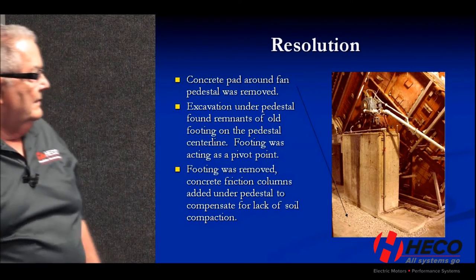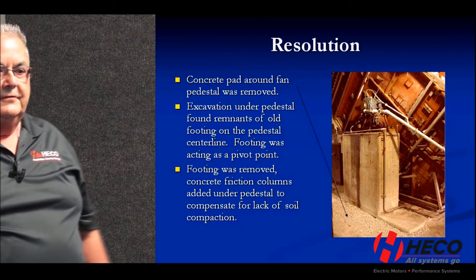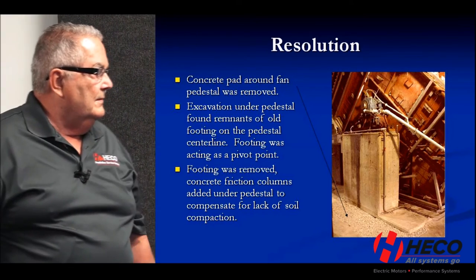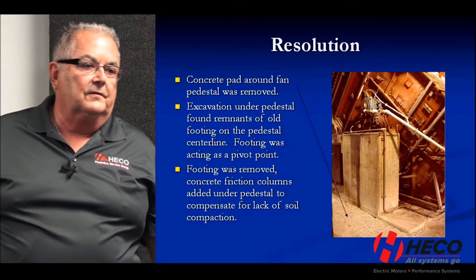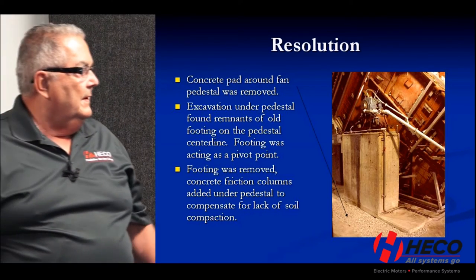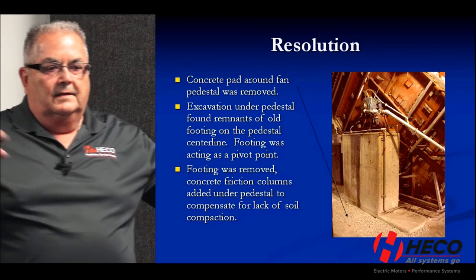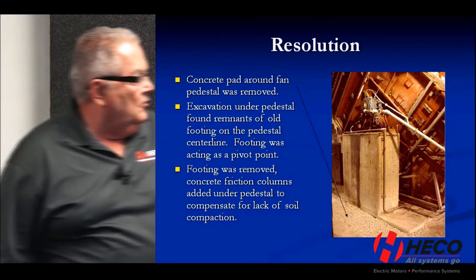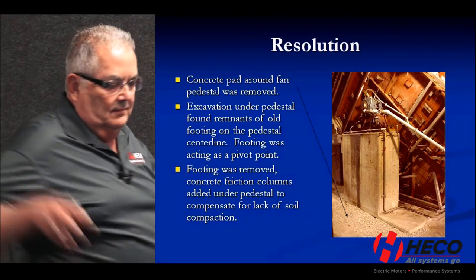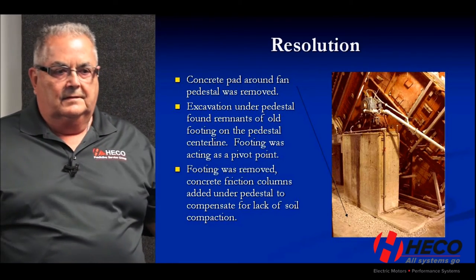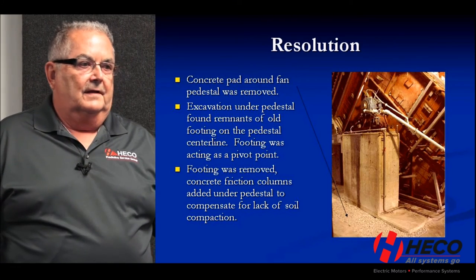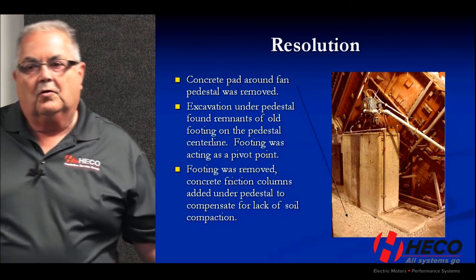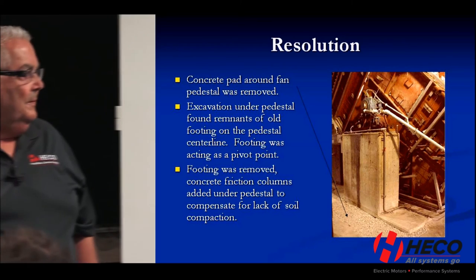We suspected that the footing hadn't been removed and that we now had a fan teetering on top of that wall. So we broke out the concrete and dug underneath — and sure enough, that wall had not been knocked down. Now we needed a fix. They excavated and poured concrete form tubes — column piers — at each corner of the pedestal going down seven to eight feet, forming solid concrete piers for the fan to sit on so it would no longer teeter-totter.